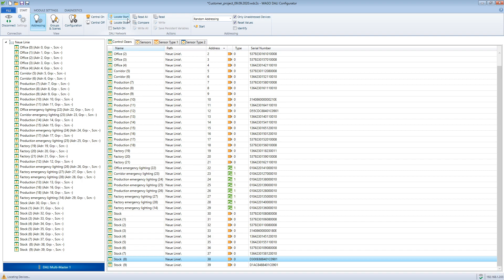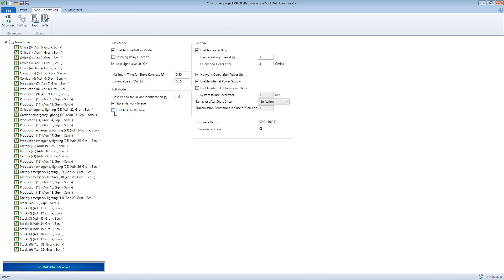If you don't have an extension of the system but want to replace a broken device, this can be done without the DALI configurator. For this purpose the function automatic replace must be activated in the module settings.